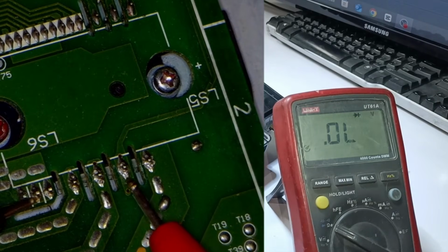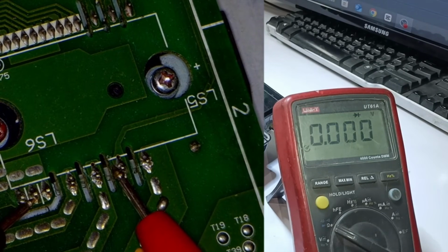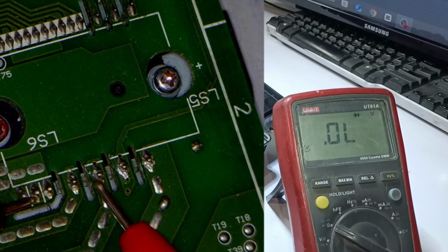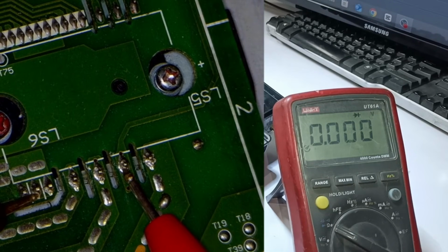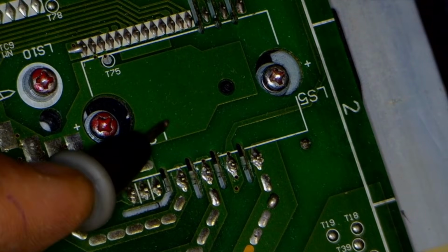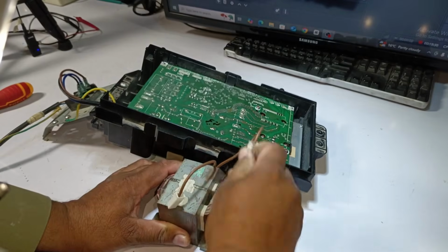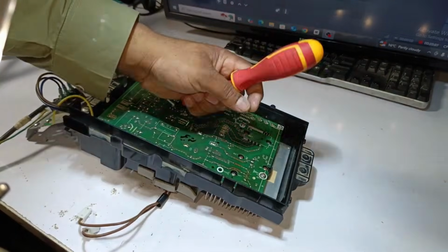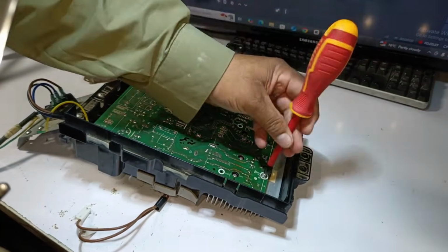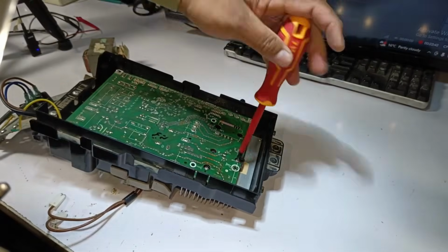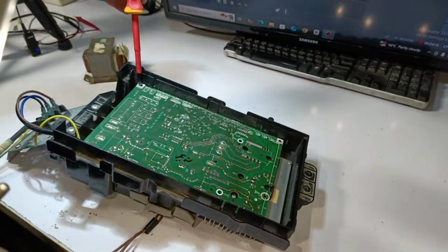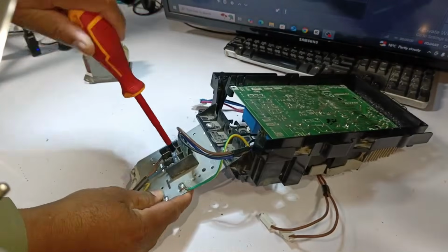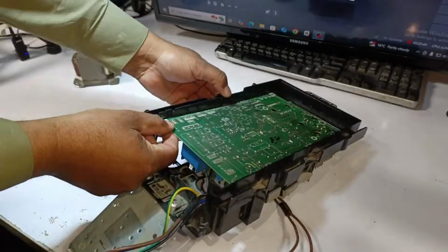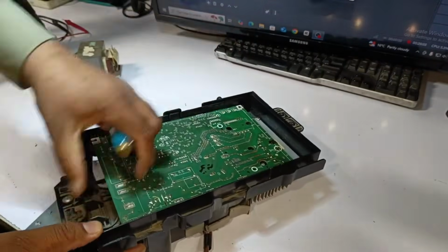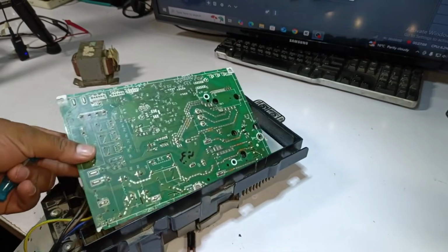However, when we checked the U point, it displayed 0.00, which indicates that the U point is faulty. Moving on to the V point, there should be no voltage drop, and similarly, the W point should also show no voltage drop. But since the U point is faulty, it means the issue is caused by the IPM. Now I'll remove the reactor and then take out the PCB by unscrewing all the screws. The PCB has been removed.